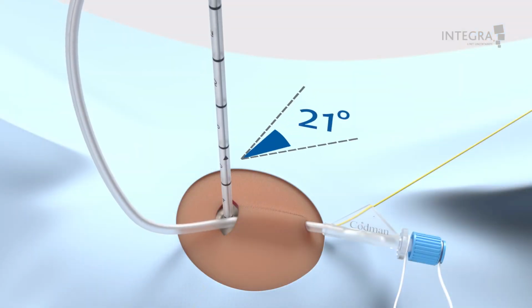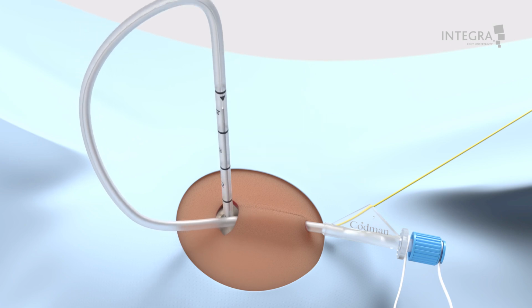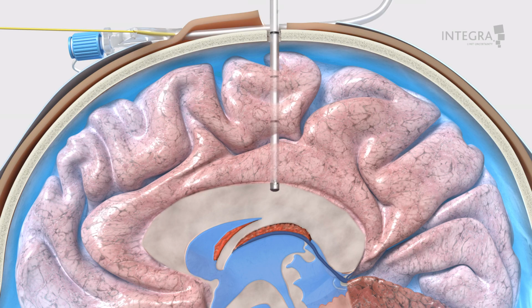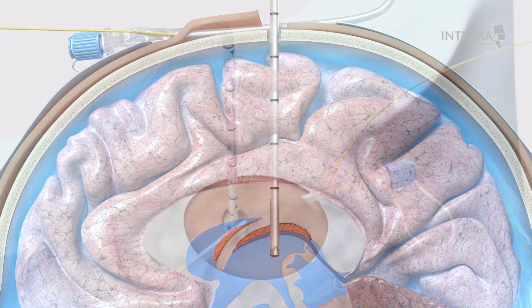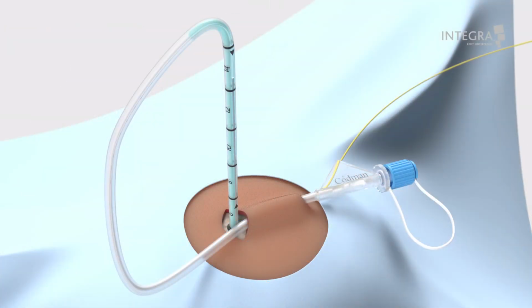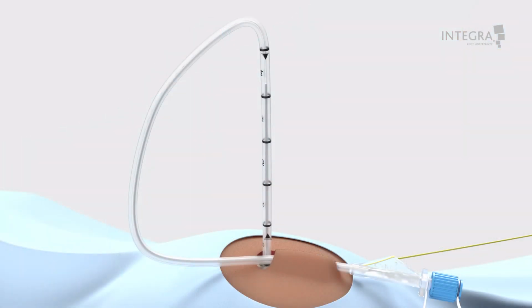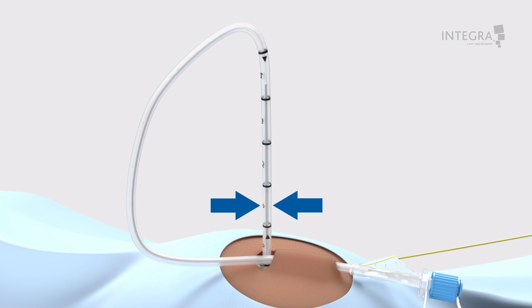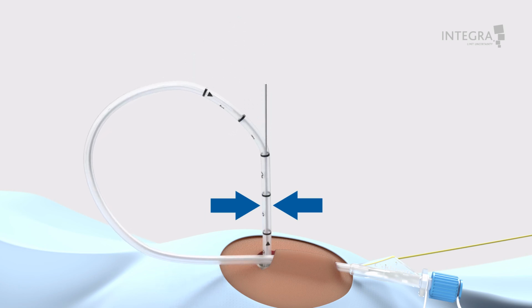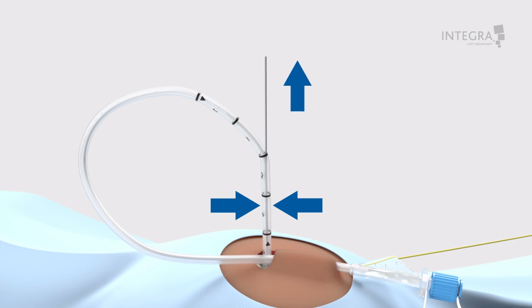Holding the ventricular catheter at a right angle to the skull, advance the catheter into the lateral ventricle to the desired depth. To verify ventricular placement, observe CSF flowing through the catheter. The black arrows indicate the portion of the ventricular catheter that has been slit for stylet removal. Holding the ventricular catheter, bend the catheter to the side opposite the 2 black arrows to expose approximately 3 cm of the catheter stylet. Holding the ventricular catheter firmly in place, gently withdraw the stylet.